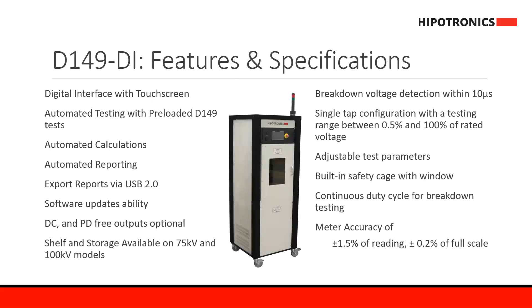The D149 DI series now has a digital interface with touchscreen controls. It has pre-loaded D149 test parameters and can also be adjusted for custom tests in case the operator wants to do a specific type of test. The system also has automatic calculations once the tests are done, and you can export data via reports through the USB 2.0 in the control. The software can also be updated via USB, and the system is now offered with DC output voltage as well as corona-free output.